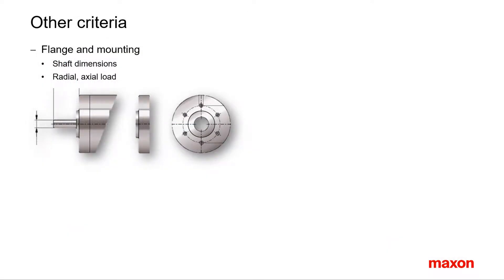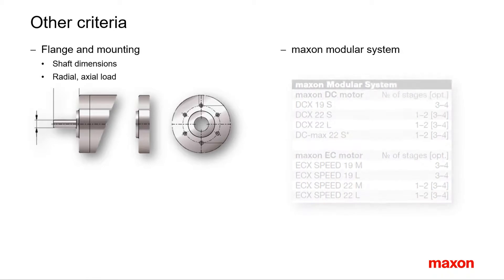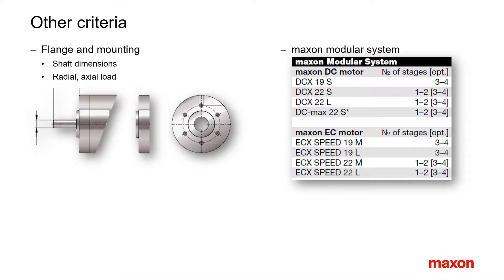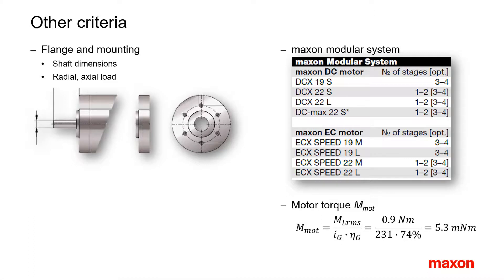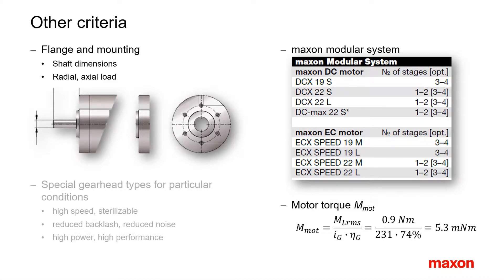In addition to considerations about torque, power, and speed, there are other criteria for the selection of gearheads. The first one is the mechanical interface: how is the gearhead going to be fixed, and how about the shaft diameter and length? Is there a flat or even a keyway needed for connecting the load? How large are radial and axial loads on the shaft? Check also the maxon modular system for suitable motor types in combination with this particular gearhead. Is it possible to find matching motors with sufficiently high torque? In our case, the RMS motor torque amounts to about 5.3 mNm. Particular conditions require special gearhead types: sterilizable versions, gears with specially high torque or high input speed, heavy duty versions for high pressure, vibration and temperature, or other special gearheads.